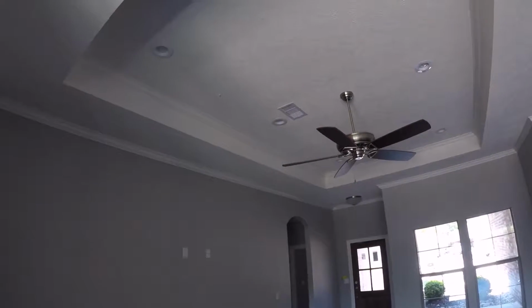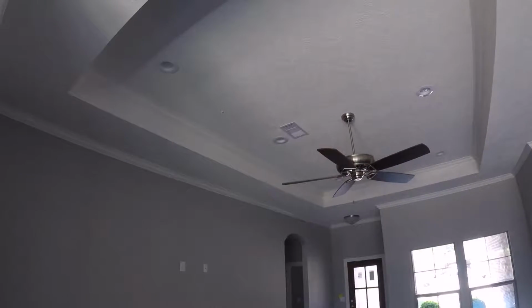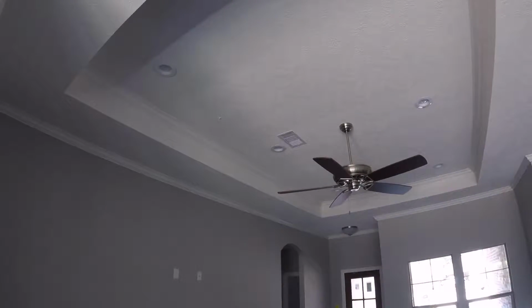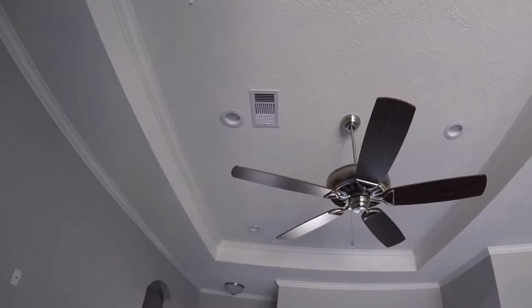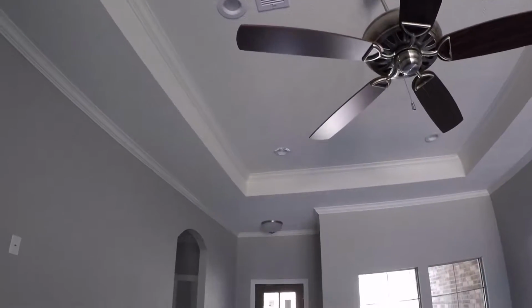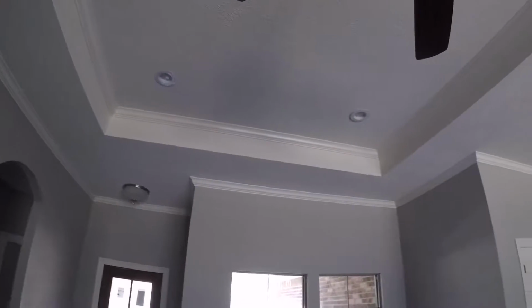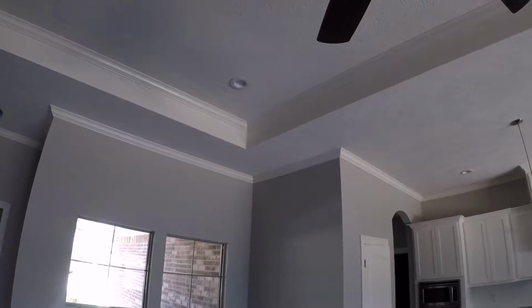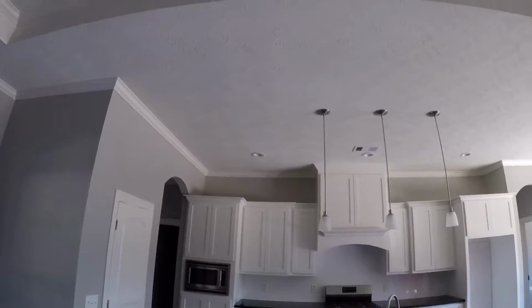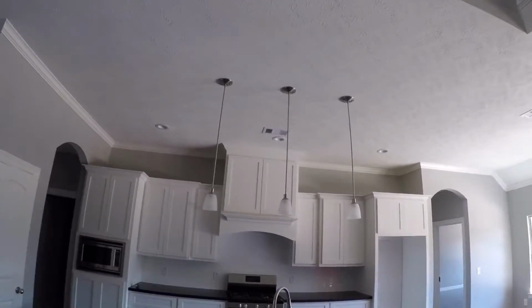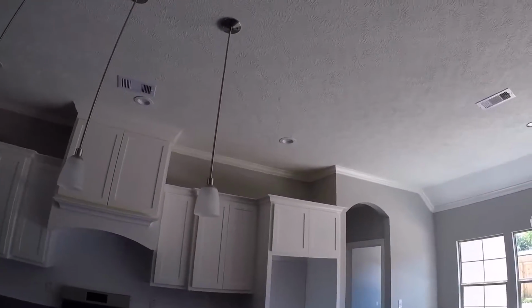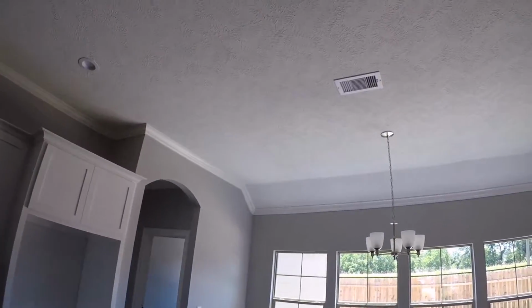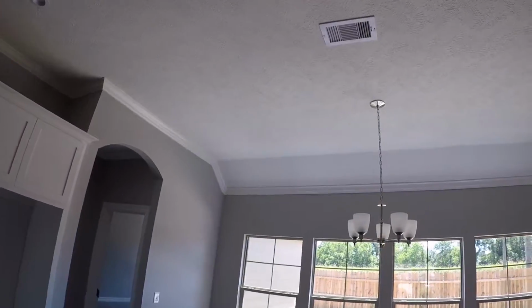One other note, I do randomly check, or just about on all of them, unless I know the contractor, and I have my thermal camera with me. We have to seal all the recessed fixtures to the sheetrock, and HVAC registers to the sheetrock, because we're utilizing sheetrock as our air barrier in homes, and that is in climate zone 2, southeast Texas, a hot humid climate. So keep that in mind. That's a big thing that a lot of the builders are not aware of. We're having to seal any penetrations in the sheetrock. We're utilizing that on a conventional insulated home as the air barrier for the ceiling.